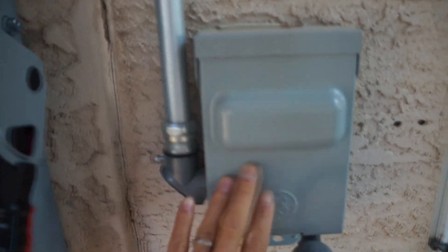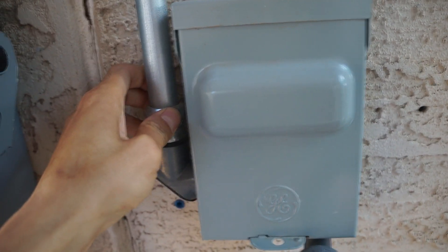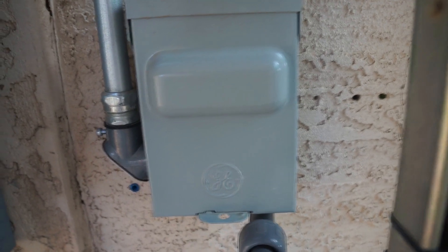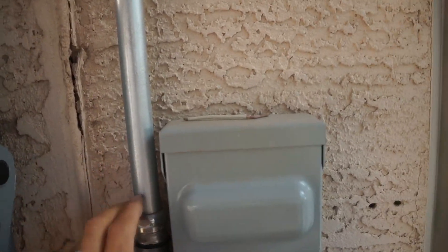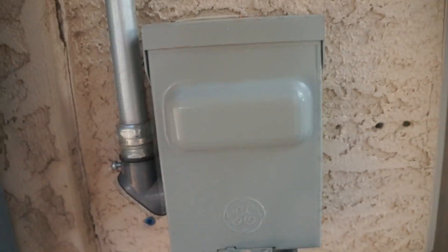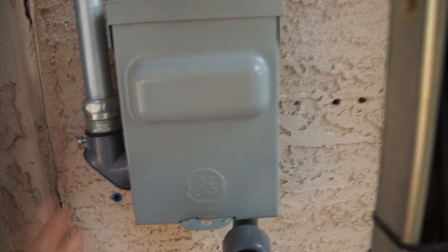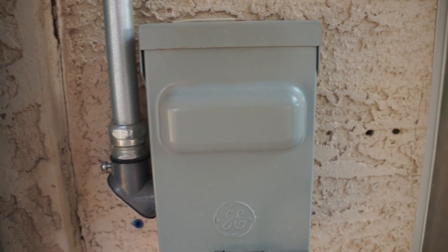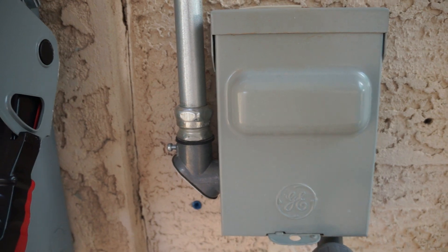When I ran the water PV conduit, I actually ran two sets of 10-gauge wire in here, so I have the option of leaving the PV water heating as-is and using the other wire. This conduit runs to the side of the house, and unfortunately my garage is on the other side, so the conduit goes to the garage for the water heating system. If needed, I could use one of those wires to power the mini-split — switching the water heater back to AC from an inverter — if I can get that system up and running.